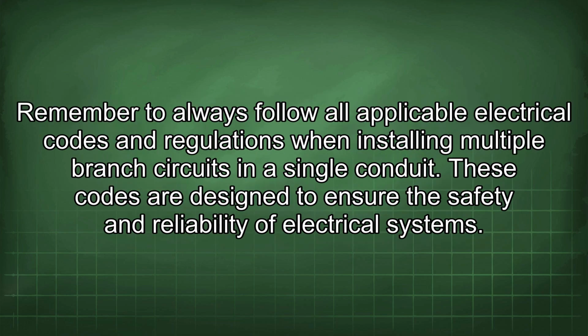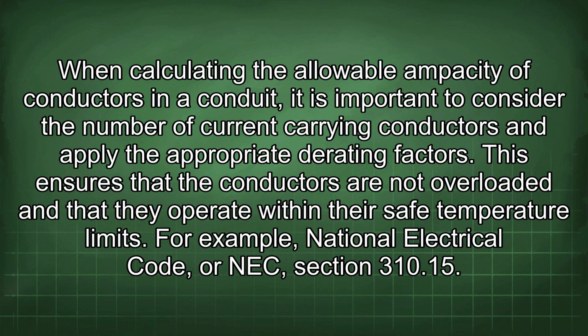Remember to always follow all applicable electrical codes and regulations when installing multiple branch circuits in a single conduit. These codes are designed to ensure the safety and reliability of electrical systems. When calculating the allowable ampacity of conductors in a conduit, it is important to consider the number of current-carrying conductors and apply the appropriate derating factors. This ensures that the conductors are not overloaded and that they operate within their safe temperature limits.